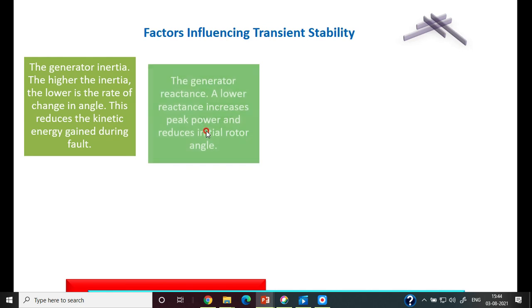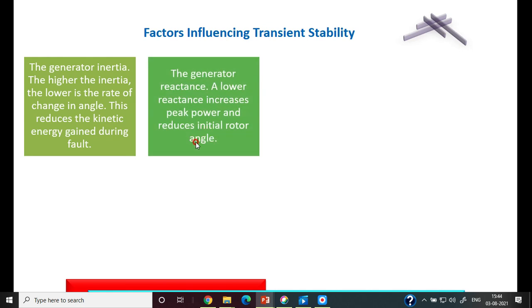Some factors influencing transient stability: first, generator inertia — the higher the inertia, the lower the rate of change of angle. Second, generator reactance — a lower reactance increases the peak power (since P_max = EV/X), meaning a lower reactance increases peak power and reduces the initial rotor angle deviation.